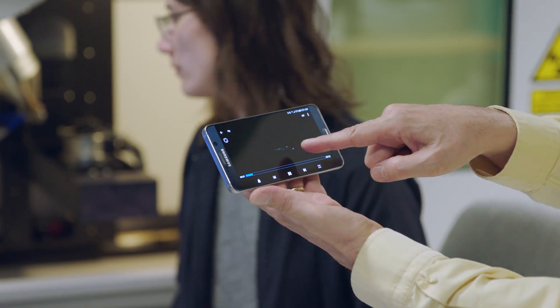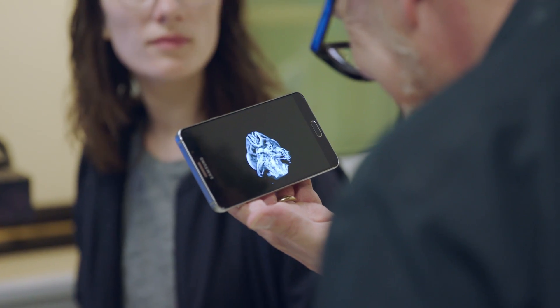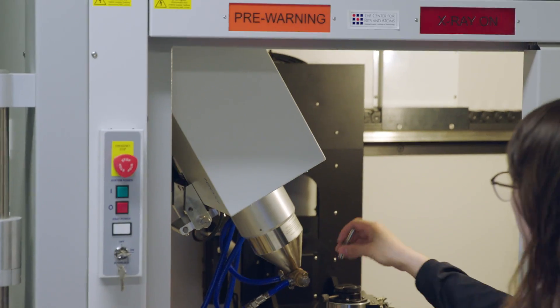This is Nadia. If you look at this, that's a 3D fly-through of the head of a house fly — made on this machine. This is possibly our favorite tool. It's a CT scanner: an x-ray with a detector at the back. You take lots of x-ray pictures and do a radon transform into a 3D reconstruction. It's an x-ray microscope that lets you see down to microns. Instead of 3D scanning the surface, this gives you the whole internal construction down to microns.